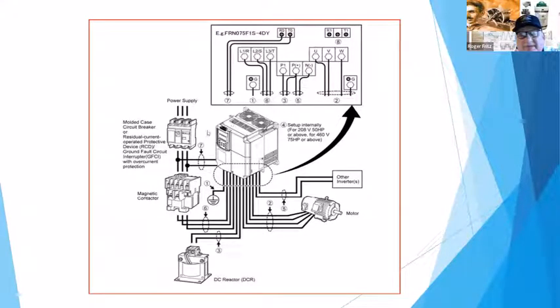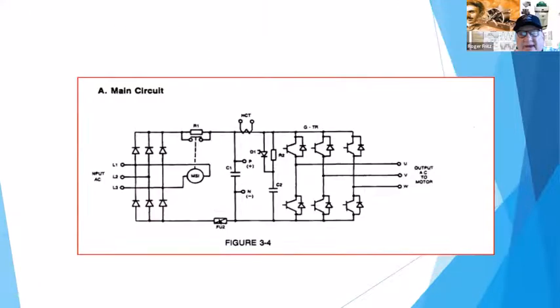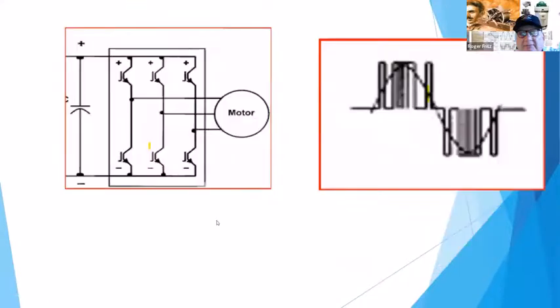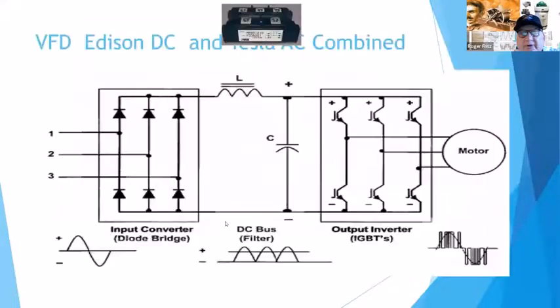Again, the same thing is you've got some sort of a disconnect switch. Sometimes they'll put a magnetic contactor for bypass in there to run directly to the motor. Then the power goes down, it goes 3-phase in, 3-phase basically out to the motor. And then you've also got connections to go out and tell other inverters what's going on. And then here's the DC reactor, which is back to the original circuit diagram here, which is very similar.